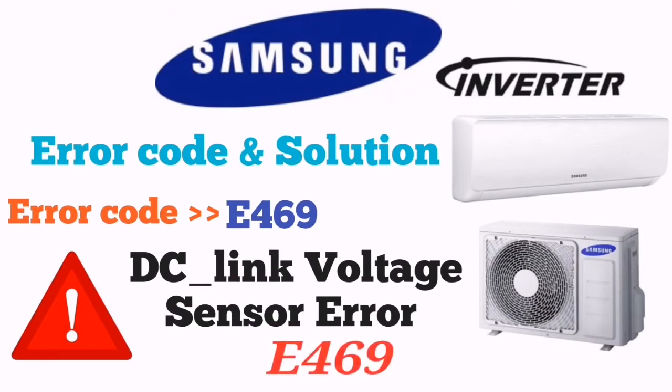When you see error E469, or LED 1 is on and LED 2 and 3 are blinking, it means DC link voltage sensor error. First of all, you have to check the connection between the reactor wire and the PCB. Try to connect it properly.